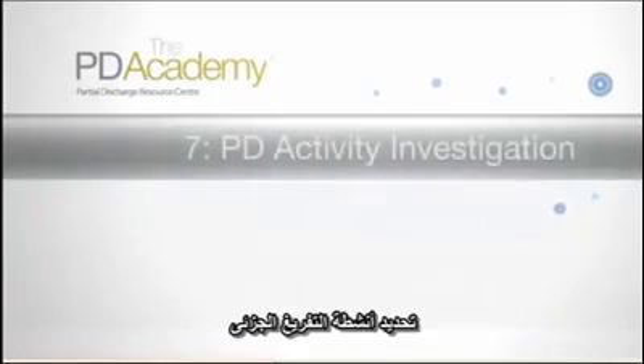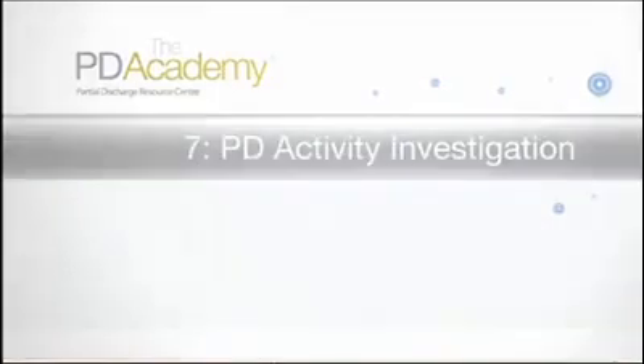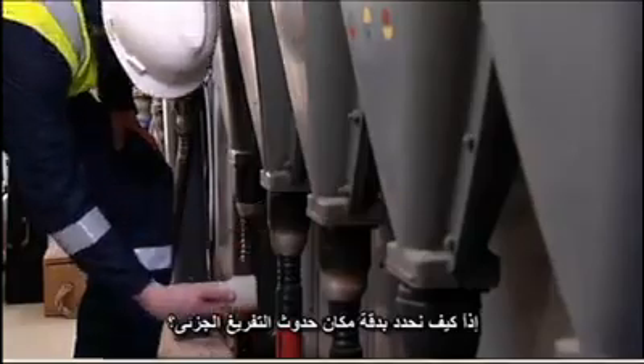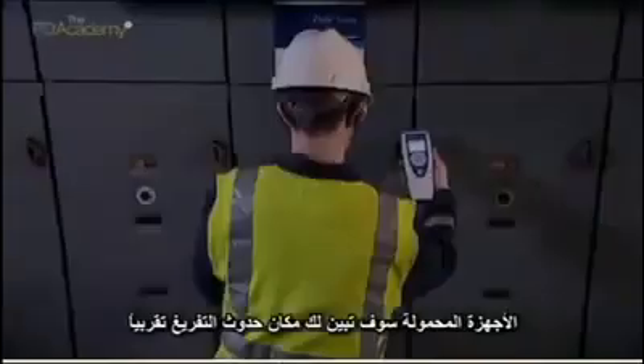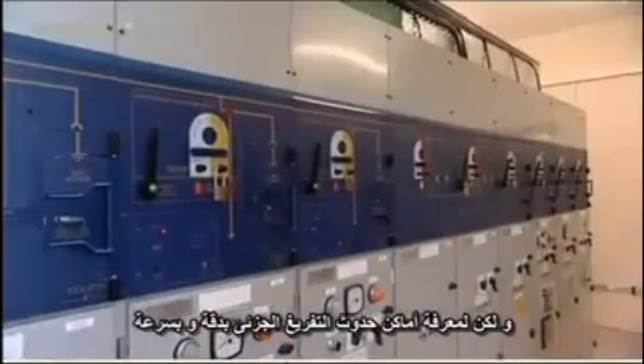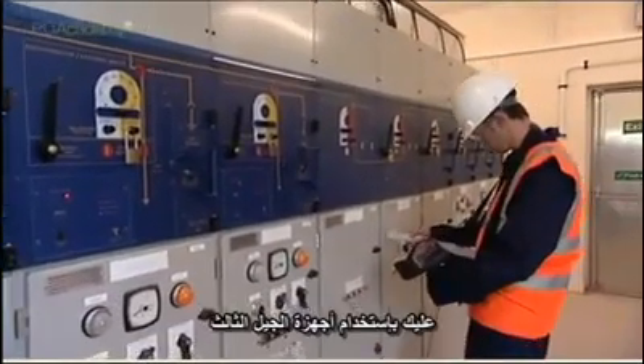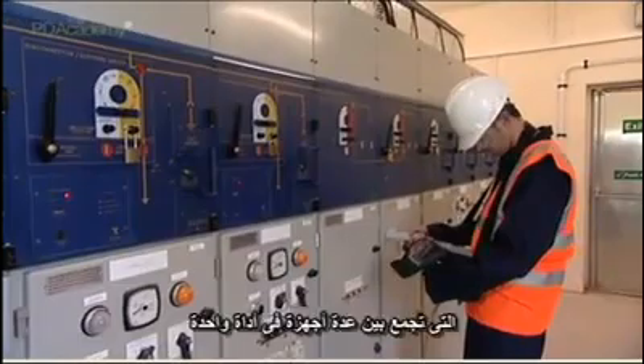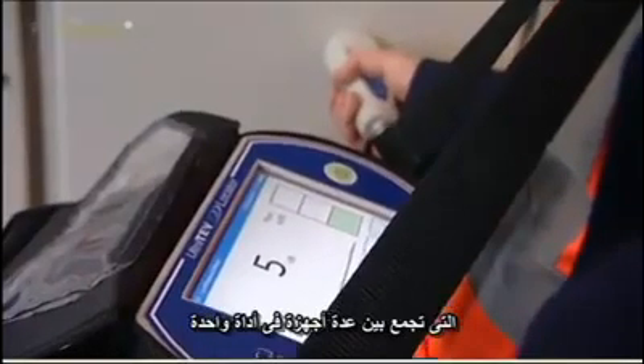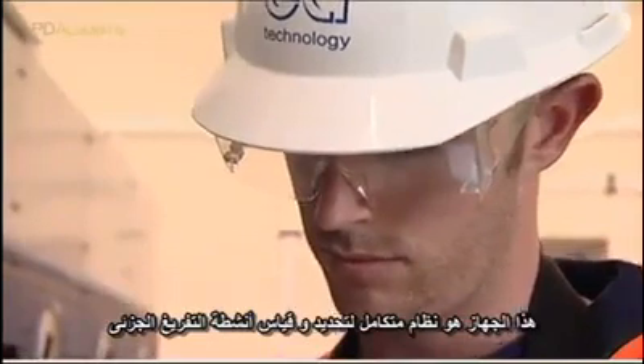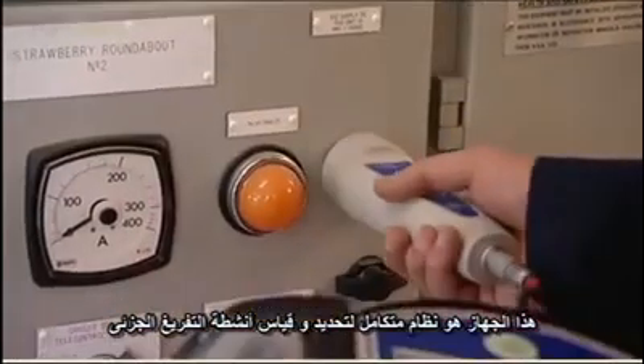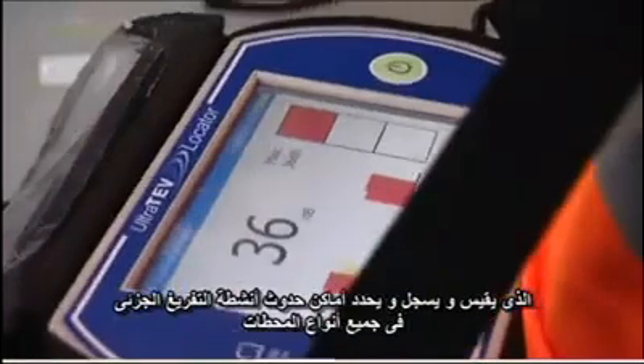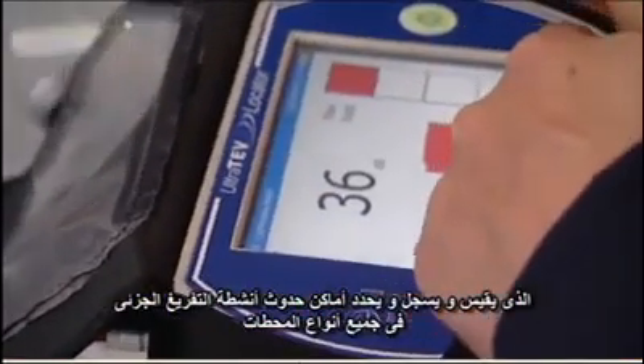PD activity investigation. So how do we locate the exact site of PD activity and investigate its magnitude and severity? Handheld instruments will get you very close to the sources of PD, but for total accuracy and speed, use one of the new third-generation systems that effectively combines several instruments in a single package. This one is a complete portable PD investigation system that locates, measures, and records PD activity in all types of substation assets, including cables.